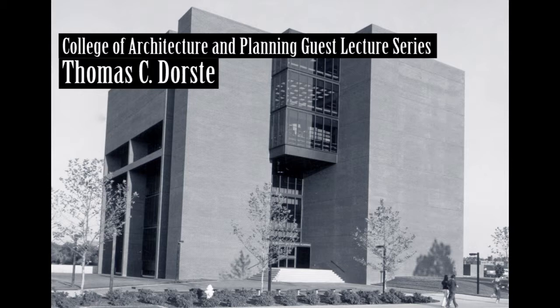The next step, and we used this first in the 1633 Medical Tower, and have used it since in other buildings, was reclamation of heat from exhaust air. That building had about 28,000 cubic feet of exhaust, and about 3,000 more supply for positive pressure. A heat wheel in that case, which takes the exhausted air to heat the incoming air before it is again heated to go into the building as makeup, saved about 750,000 kilowatt hours per year in that building. We know that. It's been in operation long enough for us to know it. And it also made us think of something else.